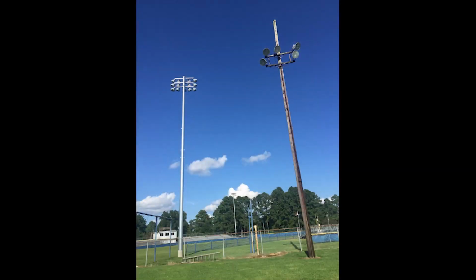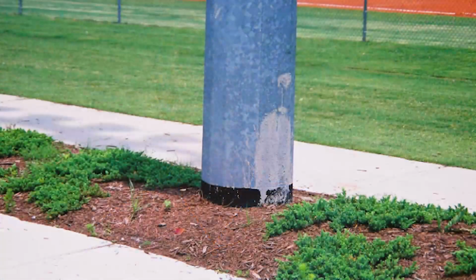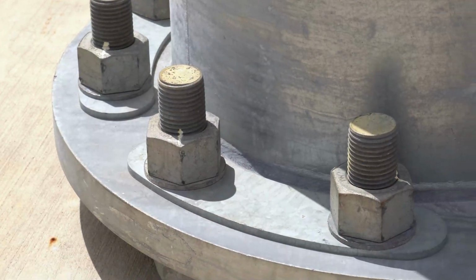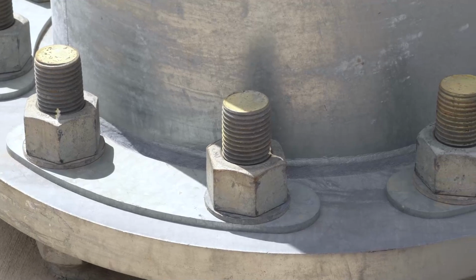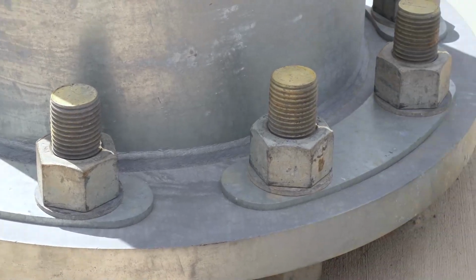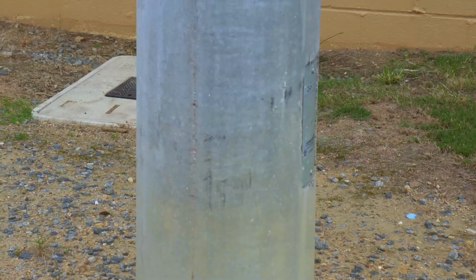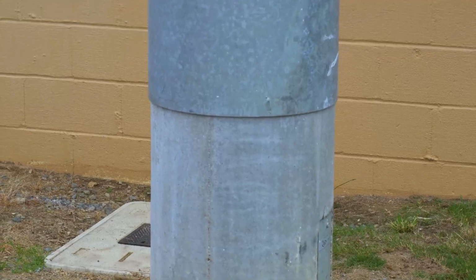Alternatives to wood poles are those made of concrete and steel. With steel poles, there are three approaches to the installation. One is burying the base of the pole beneath grade, while the other involves using anchor bolts to attach the base of the pole to a pre-poured concrete foundation. A third would be a pre-stressed concrete foundation where the steel pole slip fits over the top of the foundation.